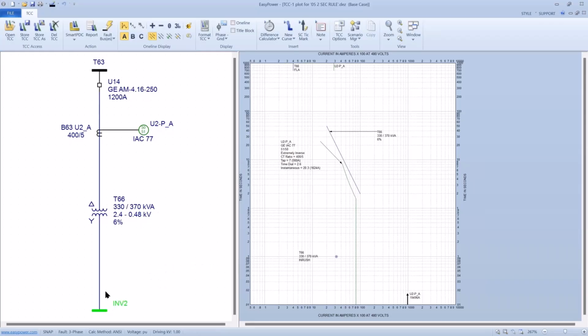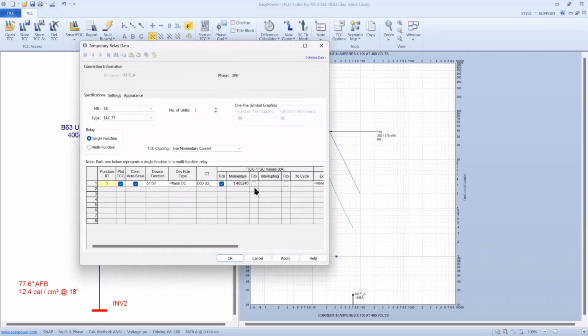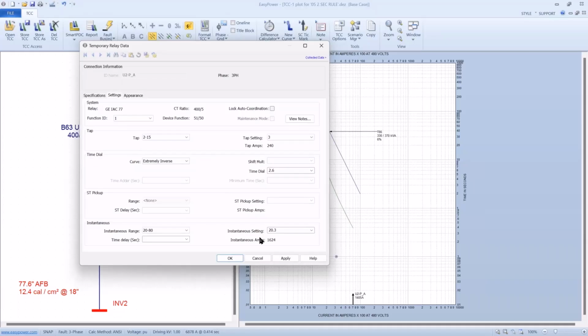And sure enough, if I fault down here, look at incident energy, I have a realistic 6,000 amps. I guess I have a problem with 6,000 amps and 480 volts and limiting it to 2 seconds, assuming someone's going to run away before they get hurt. And so what can be done about it? Well, for starters, if I don't need all this capacity on this transformer, I could lower this set point. And just by doing that, I bring my calorie rating down. And if I look at my instantaneous trip on the relay setting, look at the settings. So my instantaneous trip is at 1,000 amps, which scares me on a 480 volt system.